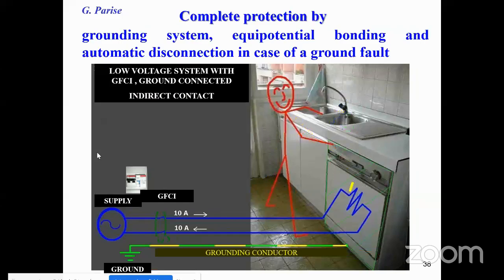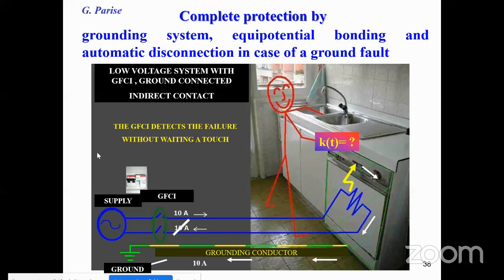In the other condition, if the exposed conductive part, the dishwasher, is connected by the grounding conductor and there is the ground electrode, when a fault happens the current immediately circulates inside the circuit. And so the ground fault circuit interrupter trips, and trips whether you touch or not. It's better if you don't touch. It's not necessary that you touch to activate the ground fault circuit interrupter to trip.